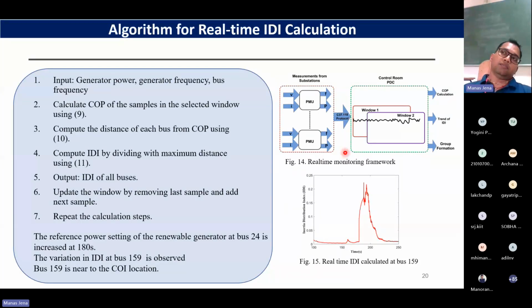As I said, this philosophy can be deployed in the control room for near real time inertia distribution index calculation. So the framework goes like this. We'll be getting the measurements from the PMUs into the control room, and we'll be deploying windows to do the IDI computation. If there is some event happening in the system, for example, in this graph, this is the real time IDI we calculated for bus 159. This bus is very much close to the center of inertia, so the IDI value is very close to 0.